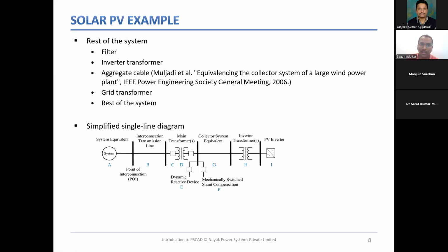So the rest of the system, again, it will have certain filters, inverter transformer, everything will be clubbed as one of each of the component with the aggregated impedances of those components. And your simplified plant diagram or SLD will look something like this. So we'll look at it from the right. You have your PV inverter. This is your photovoltaic converter. Then you have your inverter transformer. This is the aggregated diagram. Then this is the collector system equivalent, aggregated cable. Then you have your filters. Then you have your main transformer. Then you have your transmission line. This is your POC, point of coupling. This is your point of interconnection. This is your interconnection transmission line. And then you have your grid. Then you have your rest of the network grid. So this is how the plant will look when you model it in the simulation.